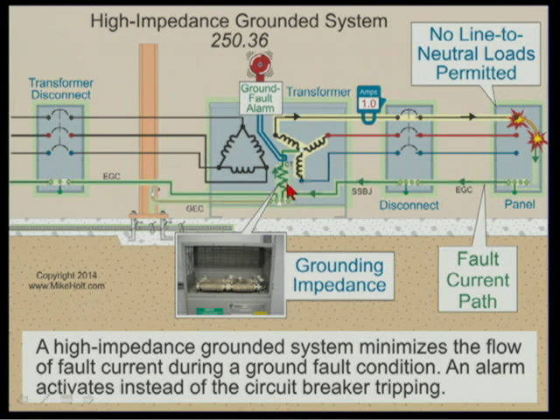You're using a resistor in place of solid, and this resistor is designed to limit the current under a fault. Watch this. When you have a fault here, now fault current comes here, it returns back to the source. This resistor typically would be rated 277 ohms, because this phase going to the case, going back to the source, which is resistive grounded, that voltage between this winding right here is going to be 277. That limits this current to 1 amp.